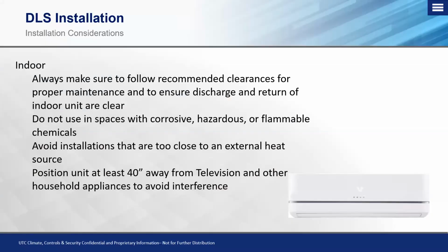So let's go ahead and dive right into it. We're going to start with the indoor unit. With the indoor unit, there are some basic considerations we need to look at when installing equipment and where the systems are going to be applied. We always want to follow the recommended installation clearances for proper maintenance and, more importantly, airflow clearance to ensure that the discharge and the return of the indoor unit are clear.